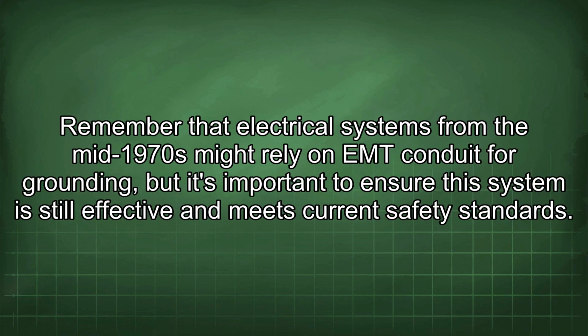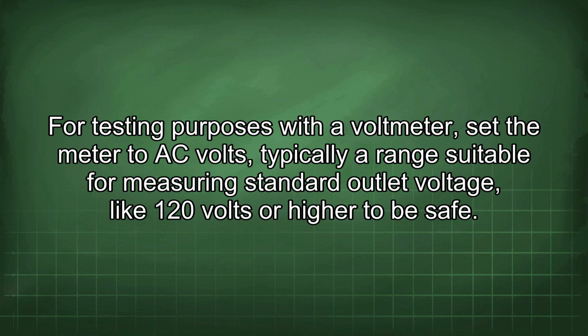Remember that electrical systems from the mid-1970s might rely on EMT conduit for grounding, but it's important to ensure this system is still effective and meets current safety standards. For testing purposes with a voltmeter, set the meter to AC volts, typically a range suitable for measuring standard outlet voltage like 120 volts or higher to be safe.